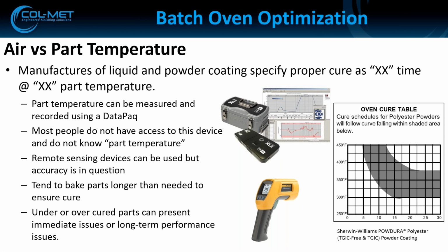A lot of people don't have access to a device like this—it's actually quite expensive. So another way people do it is they'll take maybe a temperature gun, like a handheld infrared or thermal imaging gun. They're less expensive, but also less accurate. Depending on the distance to the part, the reflectivity, and things of that nature, you can easily see temperature swings on the same part. If you measure it at the top, the bottom, or the side, you could have a 20-degree temperature difference just depending on how far away it is.